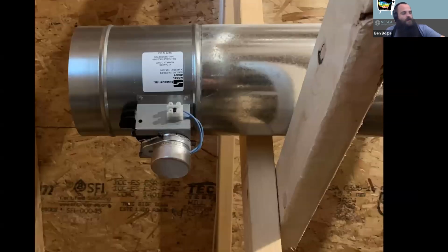This goes up here, and it's just a basic off-the-shelf 6-inch motorized damper. We do a number of different approaches. Like Ross said before, I use CT clamps sometimes to sense the current when the hood comes on, and I've used pressure switches in the past. In this case, because of how the remote blower is set up, I have a circuit that comes right off the same line as the remote blower, powering a 24-volt transformer that activates the 6-inch damper, bringing in fresh air.